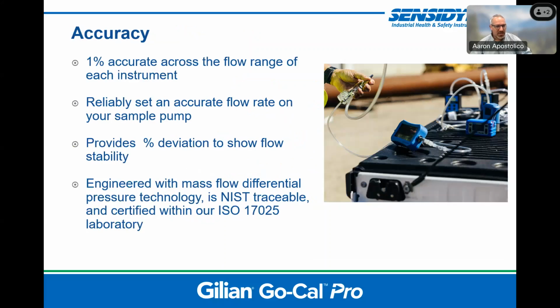So let's talk a little bit further about the accuracy of the instrument. The Go-Cal Pro is designed to be 1% accurate across the flow range of each of the instrument models. It's used to reliably set an accurate flow rate on your air sampling pump, and it can provide a percent deviation to show the flow stability.